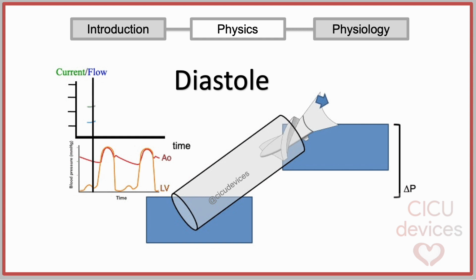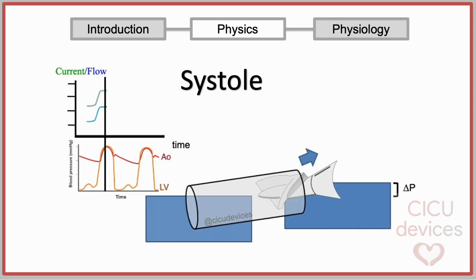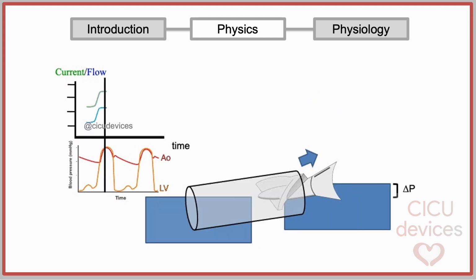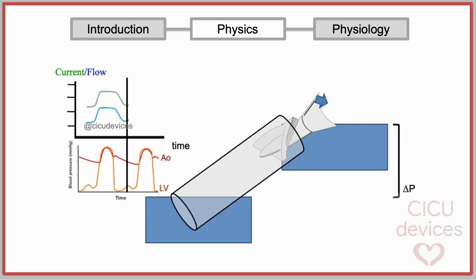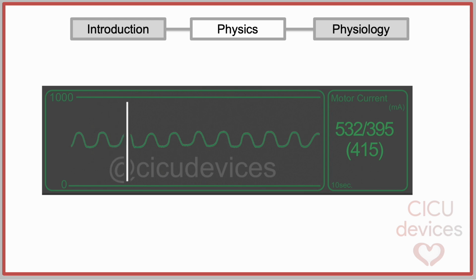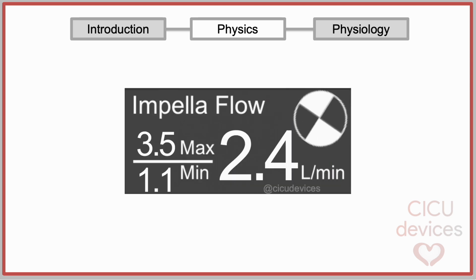When positioned correctly, the impeller operates between two chambers with dynamic pressure based on cardiac cycle. Therefore, in a catheter placed between the LV and AO, pressure difference is highest during diastole, requiring less current and resulting in lower flow. Conversely, during systole, the pressure difference is minimal, producing greater flow and consuming more current. In this way, during the cardiac cycle, there will be a sinusoidal pattern in both current and flow. Once this is known, it's not difficult to understand the current curve on the Impella console screen. It also helps to comprehend the minimum, maximum, and average flow figures that the console displays.